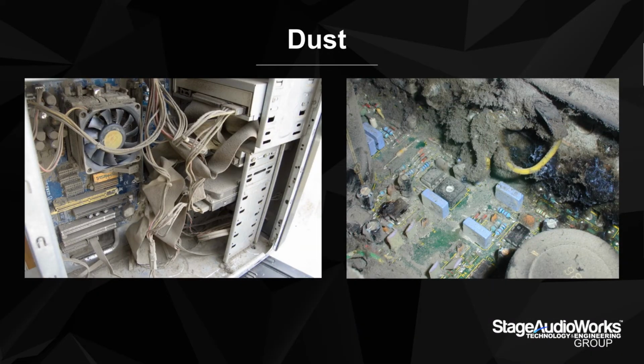If you want to clean something like this out, I would suggest using an anti-static brush and a can of compressed air, or maybe sending something like this into a service center, because they have the right tools to properly blow it out and not cause any more damage. But a blower will work well. If you're doing your own maintenance at quite a high level, a compressor will work also, but brush it off with an anti-static brush, and maybe do it outside, because I don't know how happy somebody will be inside a church if you blow all this dust onto the carpet.